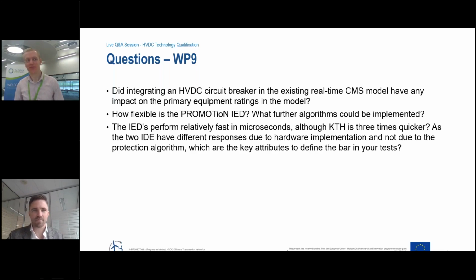The algorithms between them are slightly different as well. Ilka's KTH really does have a wider variety of algorithms; ours is more specific. I guess it comes down to some difference in hardware implementation. As we mentioned in our presentation earlier this week for 9.4, there is a redundant architecture, so that inherently takes more time with cross-validation of measurement and computation, causing some extra delay, as well as the kind of hardware level being used. Rather than being prototype level, it's industrial grade, which means you have to take care of things like overheating and cooling when it comes to the CPUs.